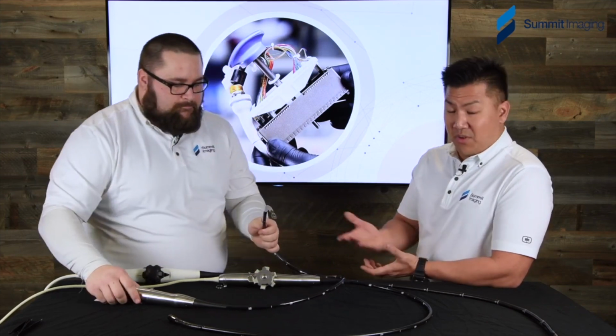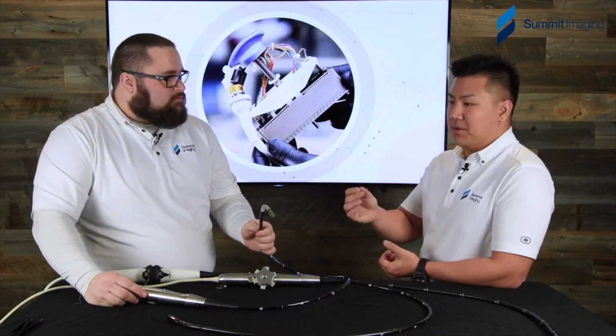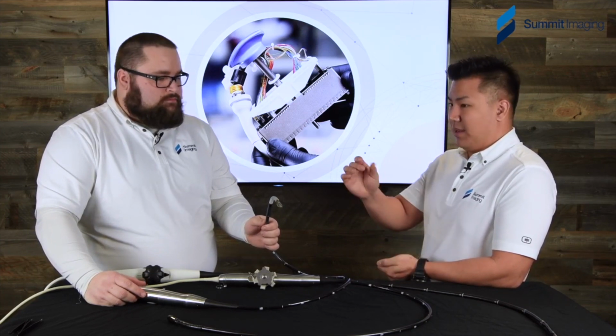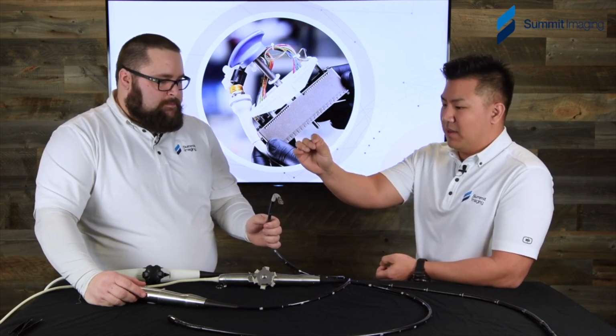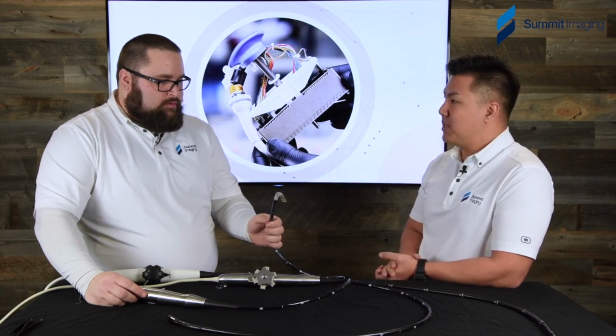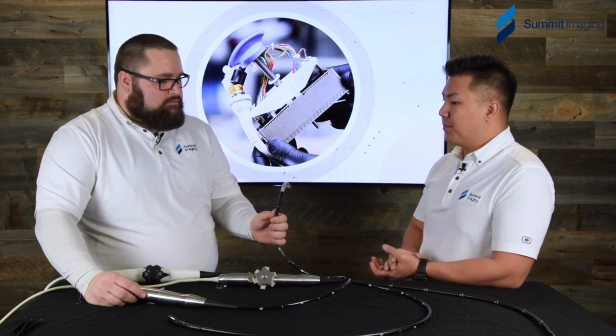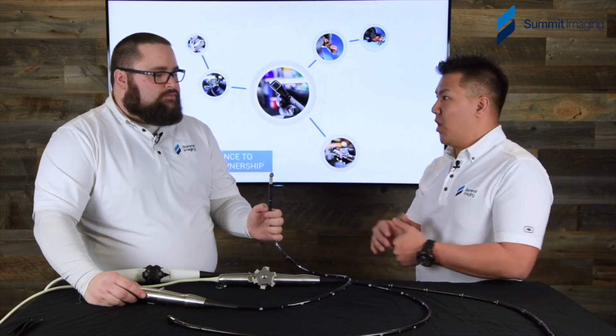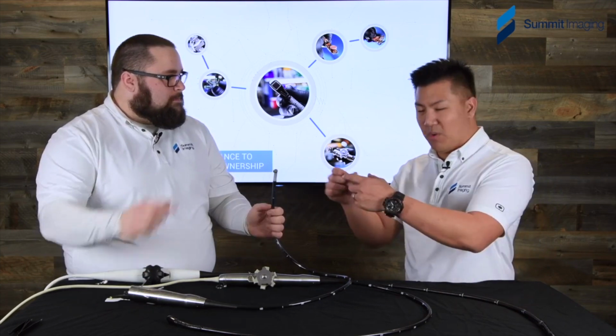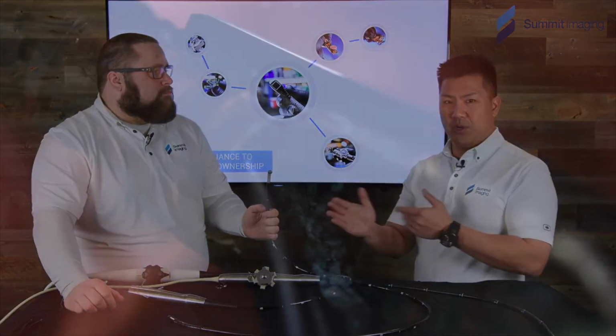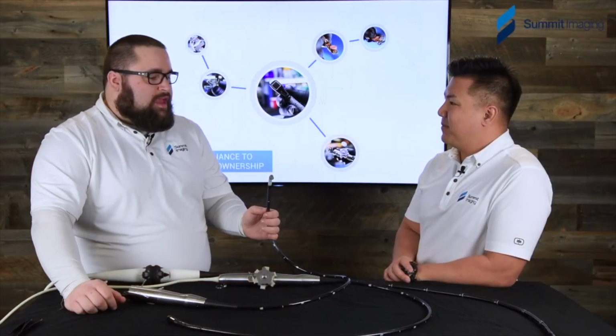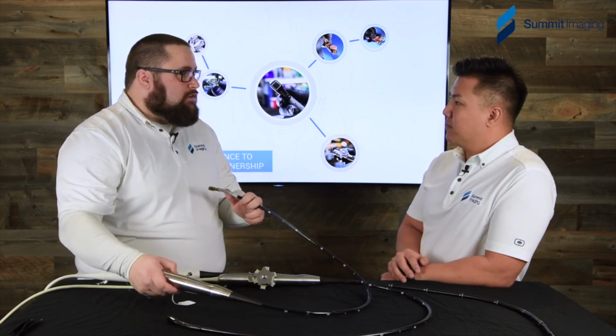Yeah, I think during our training for our internal probe technicians here, we actually demonstrate, we take a pipette and we take just a little bit of rubbing alcohol and we just put one drop on that small PCB there and the entire bank of lines that are soldered, which are about 26 to 28 in one small little area, the entire thing is now shorted. All the signal lines are now shorted to each other from one drop. Very quickly. From a pipette. And it just acts like a sponge. And it's conductive. Well, and even one of the best ways to store these is hanging. So even if you get some fluid in your handle, guess where it's going, right?